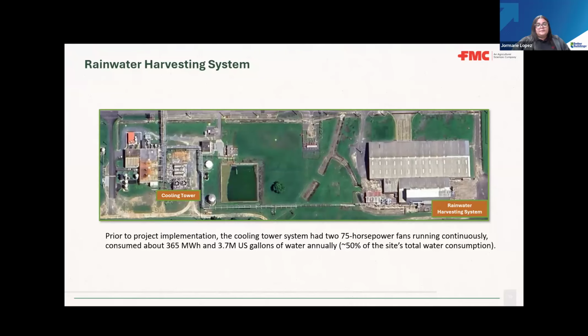Prior to our project implementation, the cooling tower had two 75 horsepower fans running continuously that consume around 365 megawatts per hour and 3.7 million gallons of water annually. This represents around 50% of our site total water consumption. So the goal of this multi-stage project was to validate low cost and easy to implement opportunities for rainwater harvesting. And with the VFD installation, we ensure overall savings and improve energy and water efficiency.